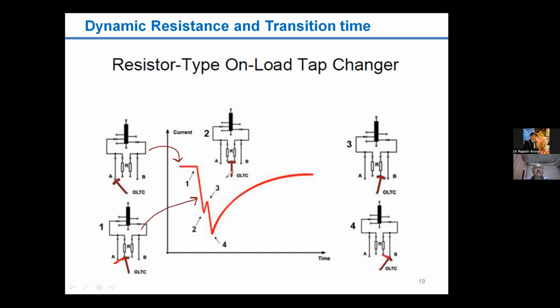During this time, you see that the transition resistance is in two parts, indicated in two portions. The first portion of the transition resistance will come into the picture with the winding, so a drop in the current will take place, which is indicated in the figure as a drop from 1 to 2. When the next position takes place, position 2 indicated just above the graph, the two half portions of the resistance will be short circuited, and a slight increase in the current will take place.